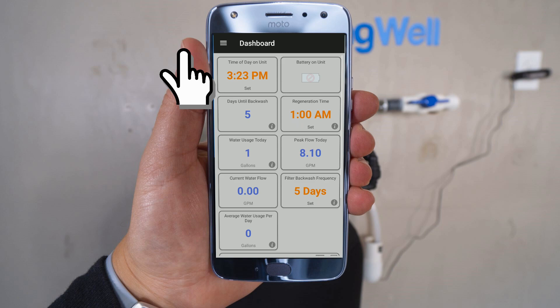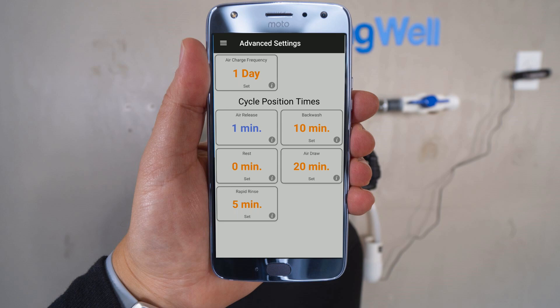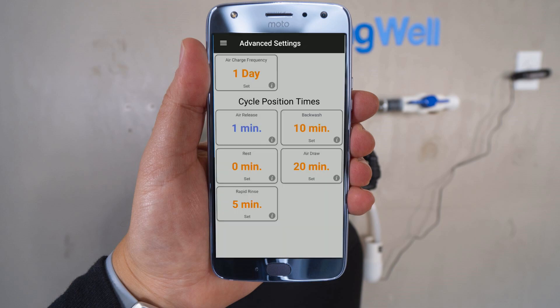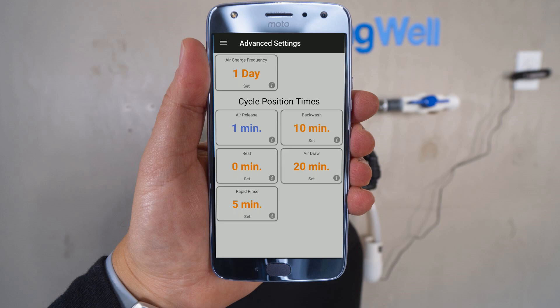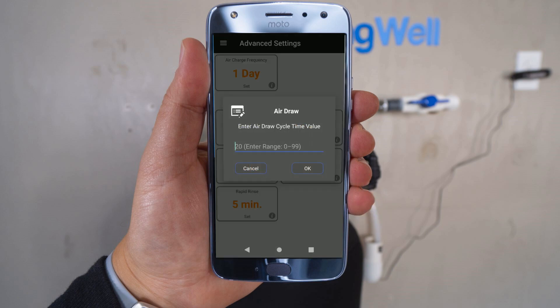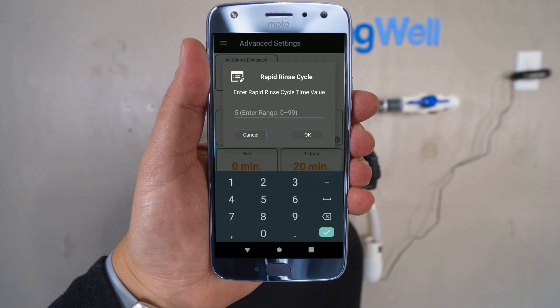For the next settings, select the menu icon in the top left corner, then select Advanced Settings. The Air Charge Frequency in the upper left-hand side should be set to 1 day — if not, go ahead and set it and select OK. The backwash time on the right column should be set to 10 minutes; update if necessary and select OK. The Rest option on the left column should be set to 0; correct if needed. Air Draw on the right-hand side should be set to 20 minutes — select it and update if not already correct. Rapid Rinse on the bottom left column should be set to 5 minutes; update if needed.